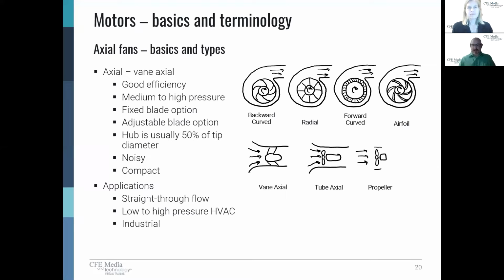Now, these are really handy because they're easier to make adjustments. You can change the blades, you can change the quantity of blades, you can change the blade shape. They're really good for high flow, and they're also good for high pressure applications. It's also the most efficient axial style because I have more control over the way that the blades are oriented, and my blade size is based on the length, not necessarily the surface area. They tend to be pretty good for high efficiency.